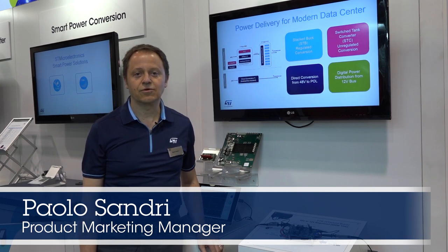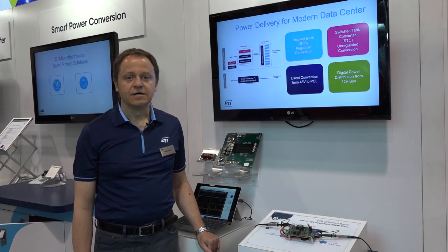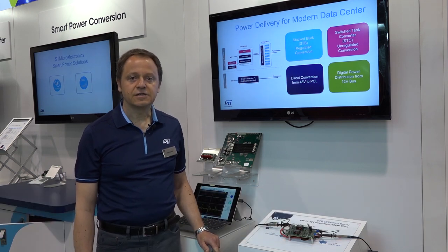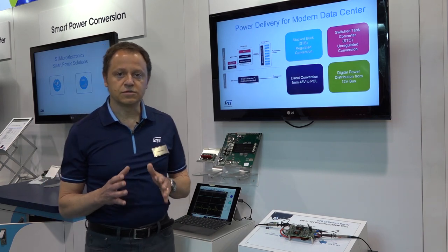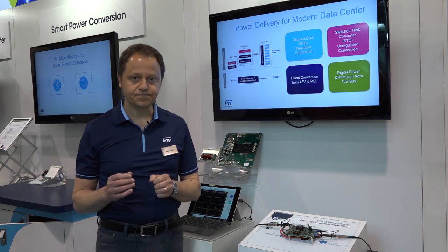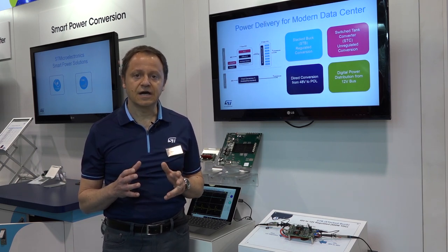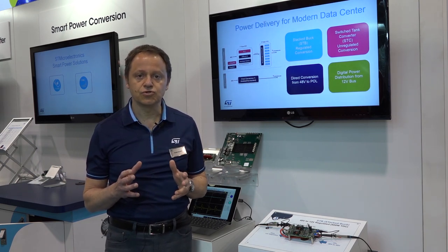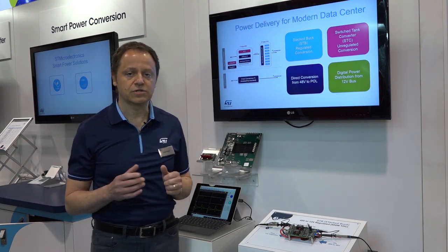Hi, I am Paolo Sandri with STMicroelectronics and today I'm going to talk about DC power distribution for data center. The recent increase in power demand for the digital ASIC is pushing the transition from a 12 volt DC bus to a 48 volt DC bus. The result is a higher efficiency of the power conversion which results in a better TCO for data center.